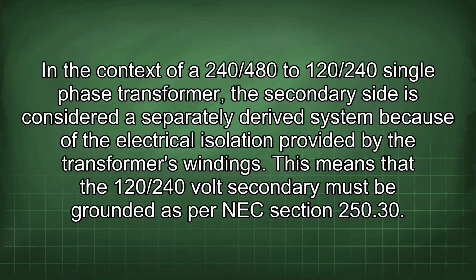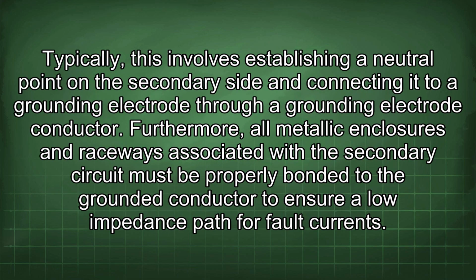In the context of a 240/480 to 120/240 single-phase transformer, the secondary side is considered a separately derived system because of the electrical isolation provided by the transformer's windings. This means that the 120/240 volt secondary must be grounded as per NEC section 250.30. Typically, this involves establishing a neutral point on the secondary side and connecting it to a grounding electrode through a grounding electrode conductor. Furthermore, all metallic enclosures and raceways associated with the secondary circuit must be properly bonded to the grounded conductor to ensure a low impedance path for fault currents.